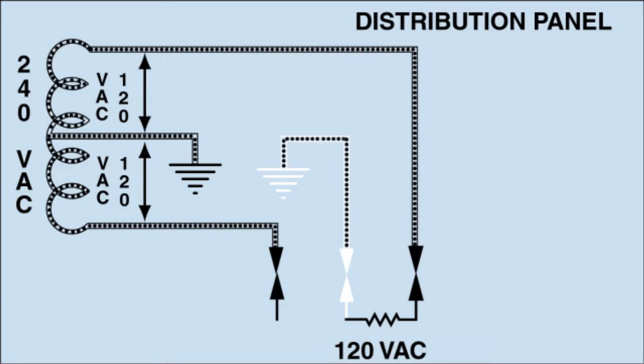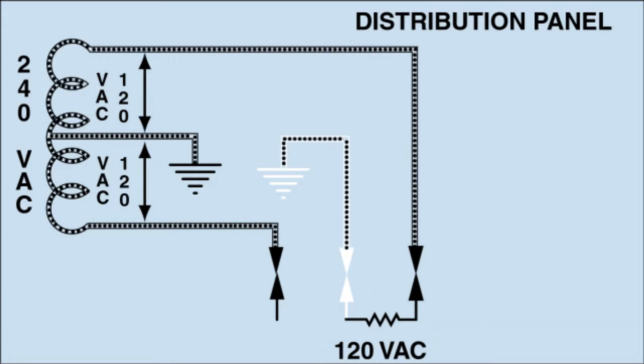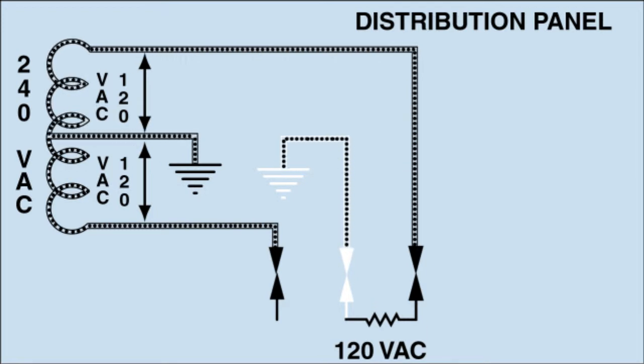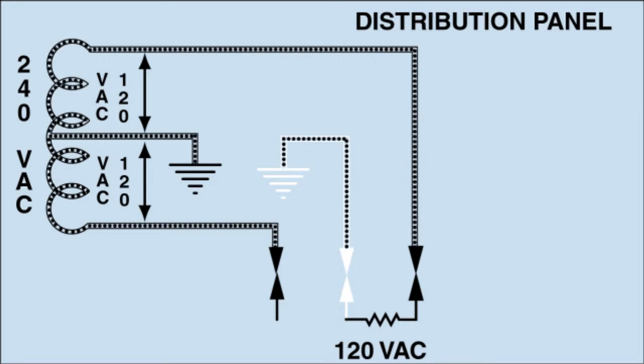If another additional exactly equal 120-volt load were placed on the other bus, then it would be the same as one 240-volt load across the secondary and there would be no current flow in the neutral from the panel to the pole.